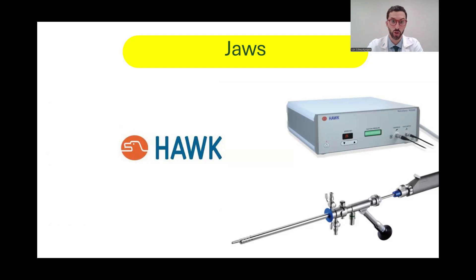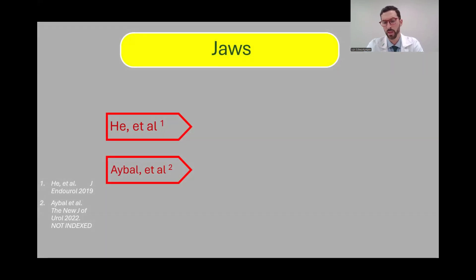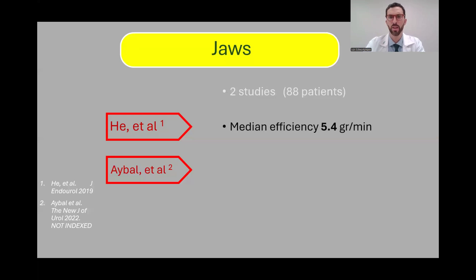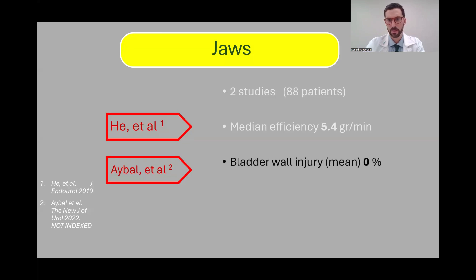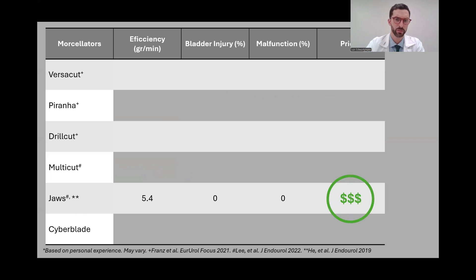The JAWS morselator is developed by the Hawk Company, a Chinese company. It functions very similarly to the Piranha — oscillating blades and a vacuum generator. There is some evidence available: one study by He and colleagues focuses on enucleation generally and reports some efficiency data, and another study by Aybal and colleagues is published in The New Journal of Urology. Two studies show an efficiency rate similar to the Piranha, with a bladder wall injury rate of 0% and device malfunction of 0%, though with limited level of evidence. It's on the higher end of the price range, though prices vary between countries and hospitals.